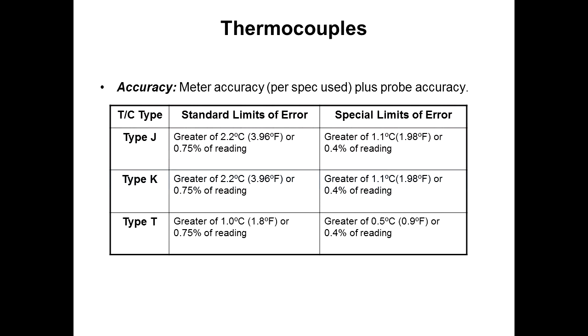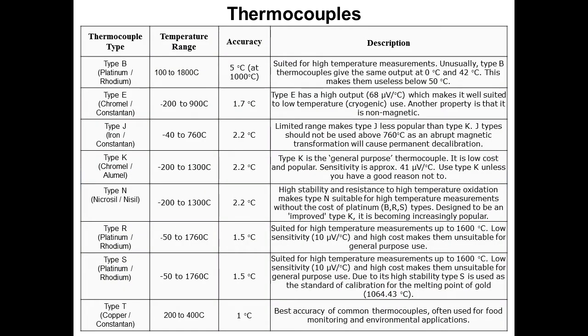But again, for precision work, you will see the wires themselves have errors that will probably put you outside of the realm of what you need. So if you use them, you have to build an offset into the meter to take care of it. These are the other types of thermocouples. We have the exotic, the noble metal thermocouples with platinum in them. And these are very expensive probes, very high temperature.